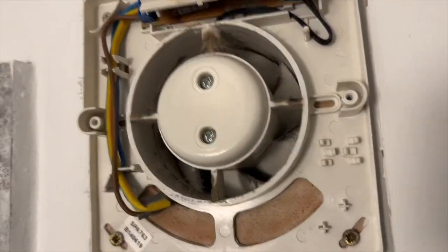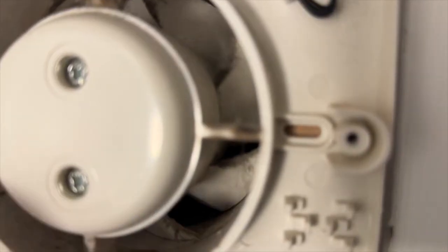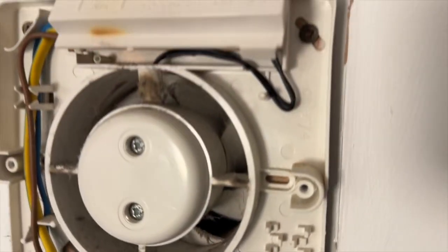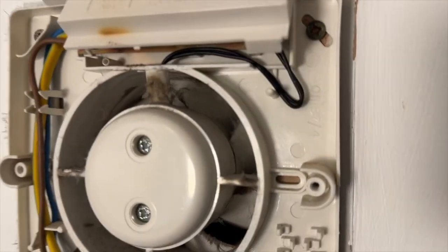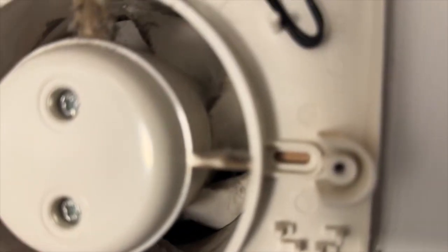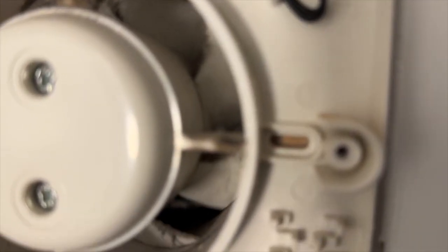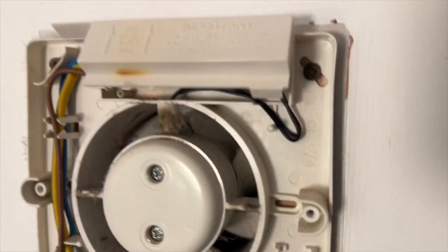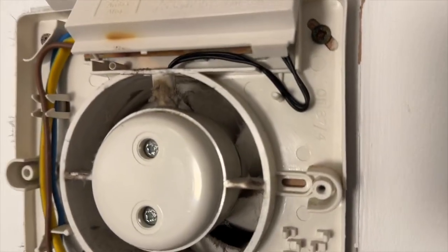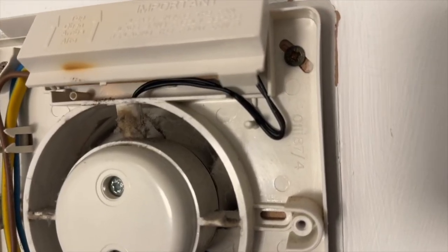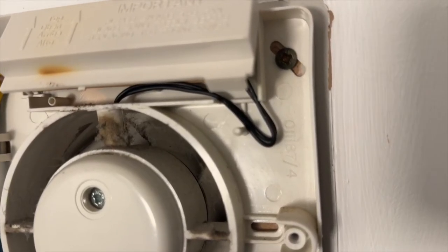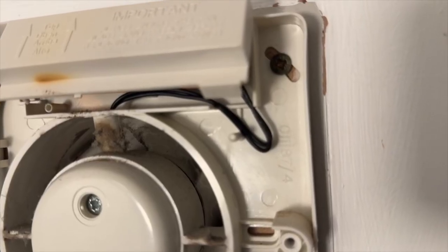Can't test the vent speed with this one, but I suspect it wouldn't. Oh, do you see that you've got the spider's webs there? Which tells me that it hasn't been running for a while. But do you see how you've got a bit of dust collecting on these? That will slow it down, and I find dust and dirt can slow it down by about 50%. Really? Over the course of maybe, I don't know, 5 years or something.